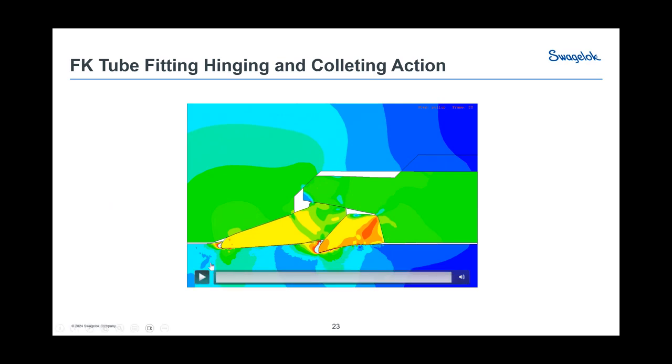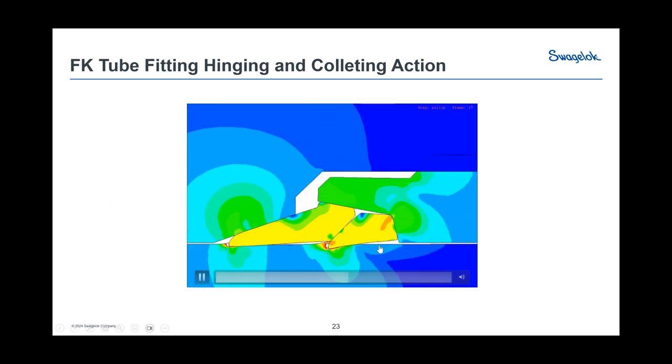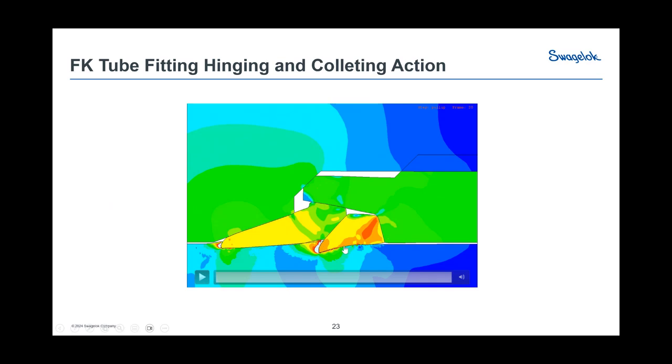And in those, you're machining it, and the outside doesn't matter. So since we couldn't be sure that the outside of the tubing was going to be in pretty good shape, we actually create our own seat along the tubing to make sure that we seal well. The back ferrule, you'll notice, is much beefier than the standard tube fitting, and it has to be because of the pressures. But it still has a colleting area in it. The bite is much more aggressive to be able to hold, and the basic functions are all the same.